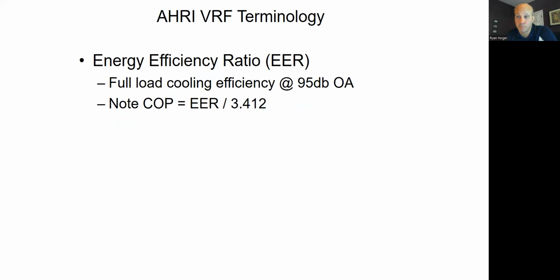A, because it's a heat pump, B, because it also has cooling, and C, because it's simultaneous heating and cooling. I get lots of rating numbers. So you get the full load EER like every piece of equipment gets you. Hey, if I ever have this 95-degree day and every single zone is calling for maximum heating and cooling, what's my EER, right? We said that day hardly ever happens, but we get that number.